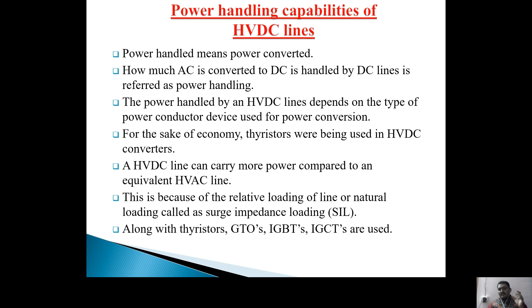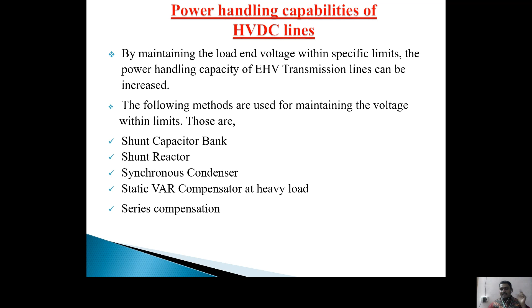Next, by maintaining the load end voltage within specific limits, the power handling capability of EHV transmission lines can be increased. EHV means extra high voltage transmission lines. We use a few methods to maintain the voltage within limits. First is the shunt capacitor bank, next the shunt reactor, third the synchronous condenser, fourth the static VAR compensator at heavy load, and fifth series compensation. By using these five methods, we maintain the load end voltage within the limits. Firstly I will start with the shunt capacitor bank.